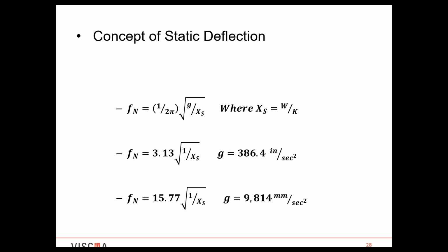Looking at just the static deflection, just from the weight itself, you can look at it in all kinds of terms. You often see it expressed in the natural frequency: f_n equals 1 over 2 pi times the square root of gravity over your static deflection, x_s, where that static deflection equals your weight in the numerator divided by your spring constant in the denominator. If you set gravity in English US customary imperial units to 386.4 inches per second squared, you can look at it in the units in the second equation here. Oftentimes that is used with consultants: 3.13 times the square root of 1 over your deflection.